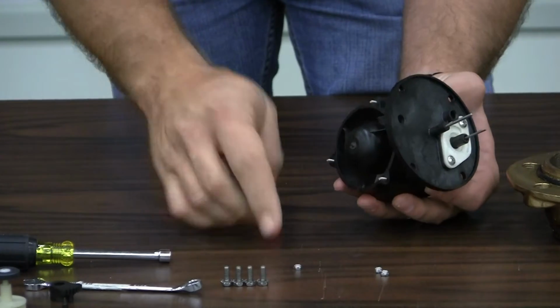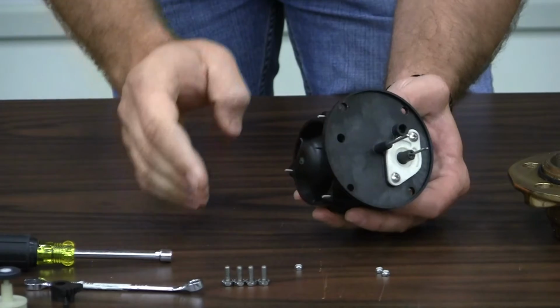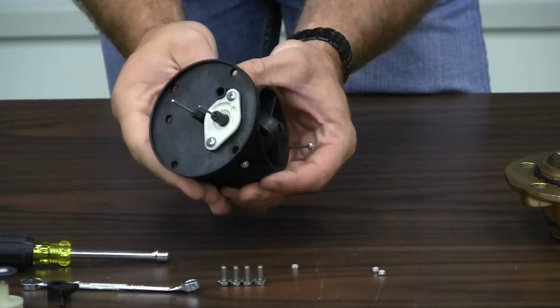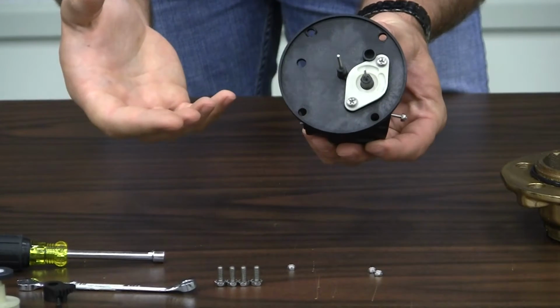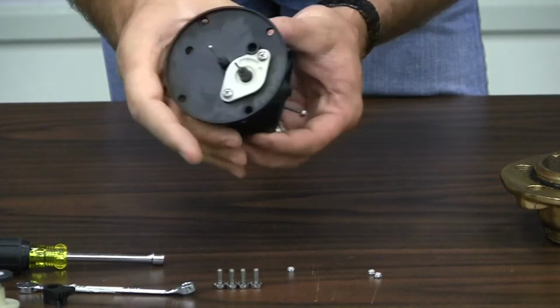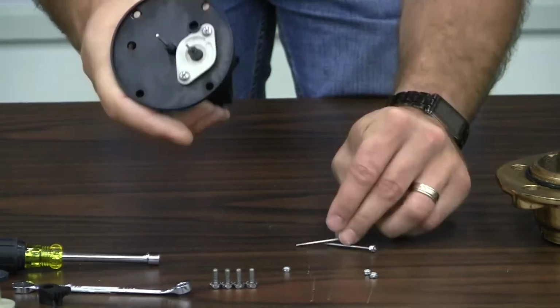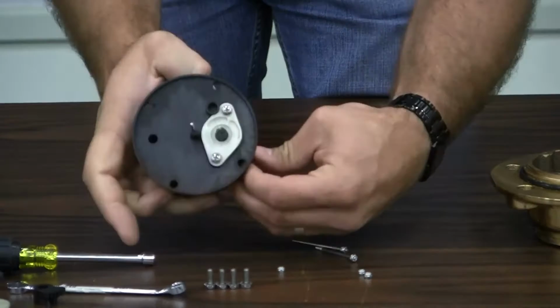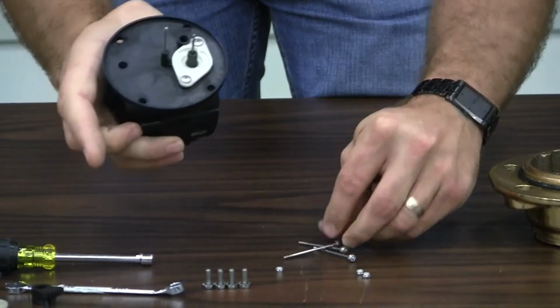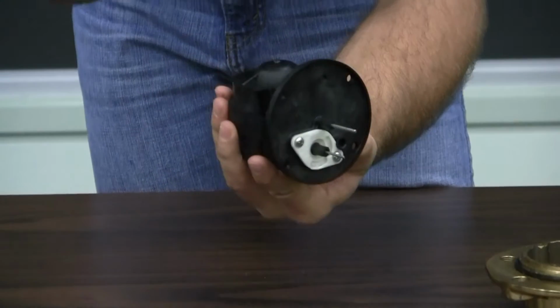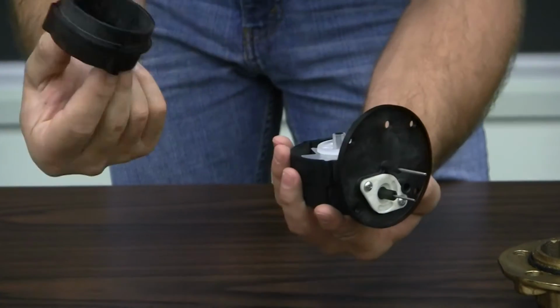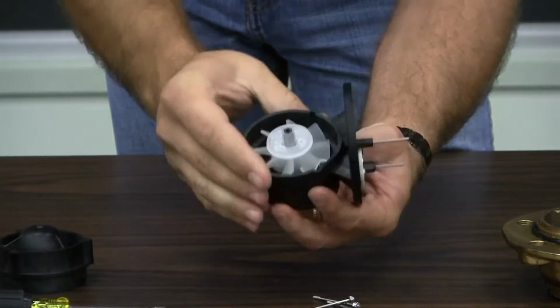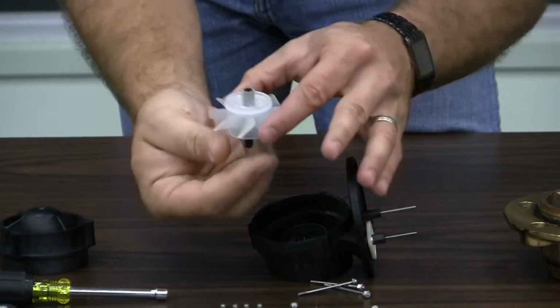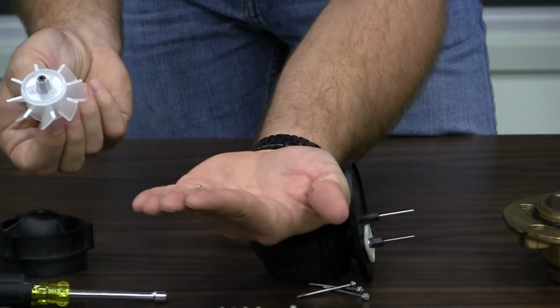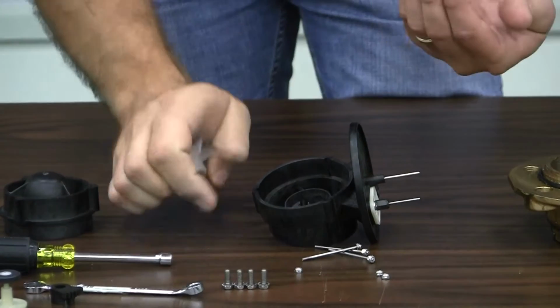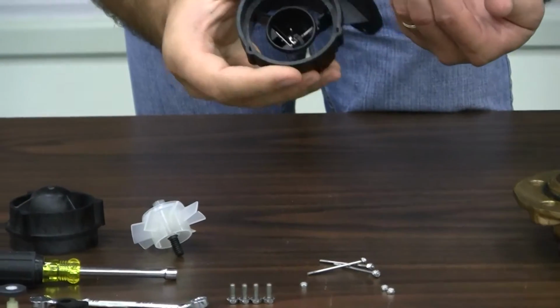I've removed the 3 1/4-inch nuts from the turbine element. At this point, you're looking at the outlet and the inlet side of the turbine element. You don't want to snatch these apart because there's a small ball bearing inside the unit. So I'm going to just slide these 3 bolts out. And I'm holding the outlet side up. I'm going to pick the outlet side up, and I can set the inlet down, but inside this rotor is a small ball bearing. And then you just have the inlet left, and you can see the gears inside the inlet.